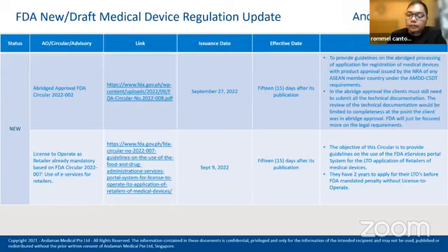CSDT requirement. In this abridged approval, the clients must still submit all the technical documentation. The review of the technical documentation would be limited to completeness at the point the client is in abridged approval. FDA will just focus more on the legal requirements and the labels. So the good thing here is that the timeline set by FDA for processing is only 30 working days. That is very fast.